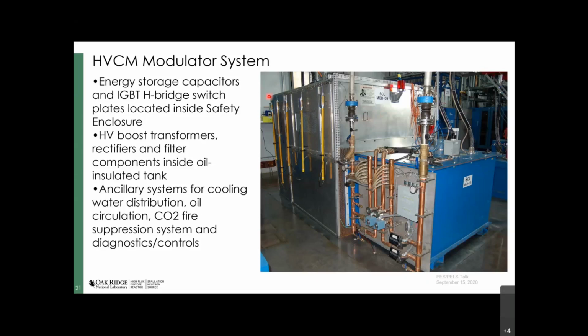That's where we create our DC link. That capacitor bank is quite large. It can store each polarity up to about 100,000 joules of stored energy, so it's quite dangerous. That's what all these yellow sticks hanging on the side are about, to allow us to safely discharge the energy associated with the system.